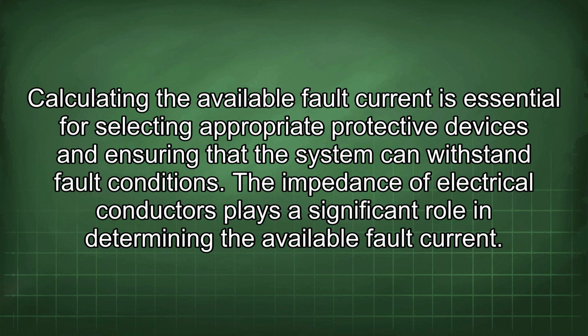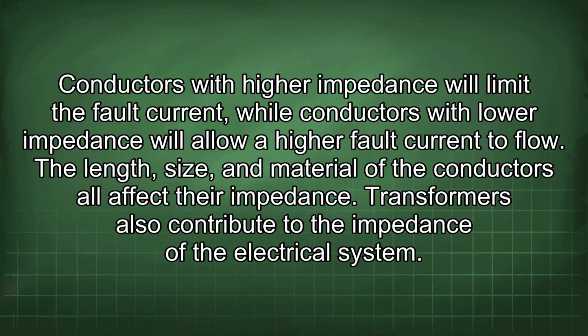conditions. The impedance of electrical conductors plays a significant role in determining the available fault current. Conductors with higher impedance will limit the fault current, while conductors with lower impedance will allow a higher fault current to flow. The length, size, and material of the conductors all affect their impedance.